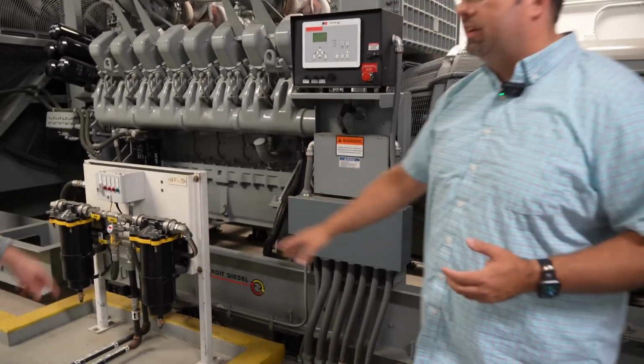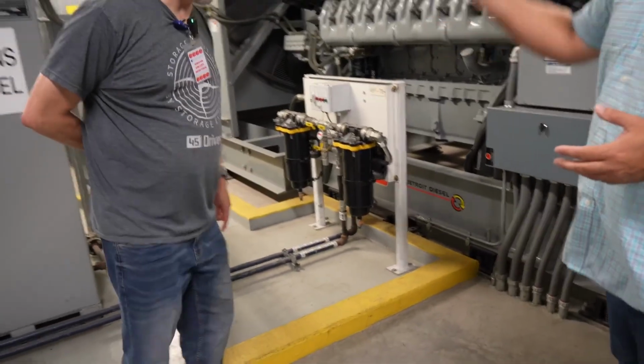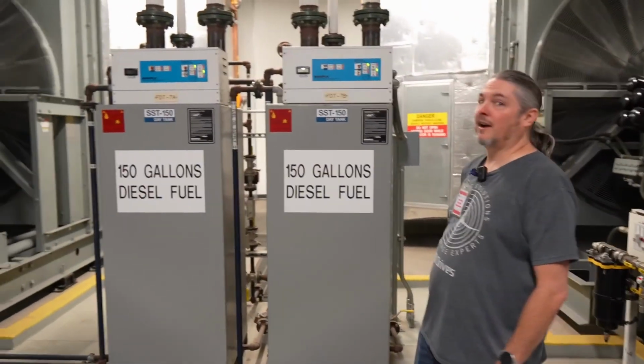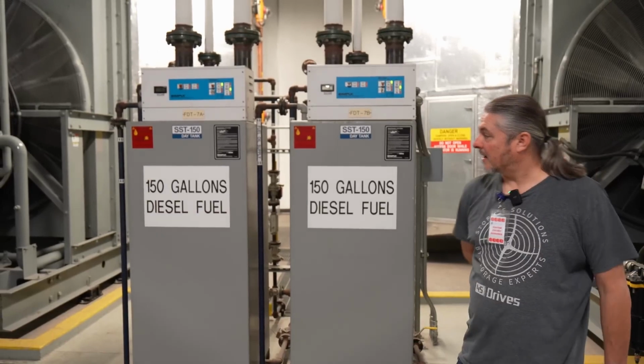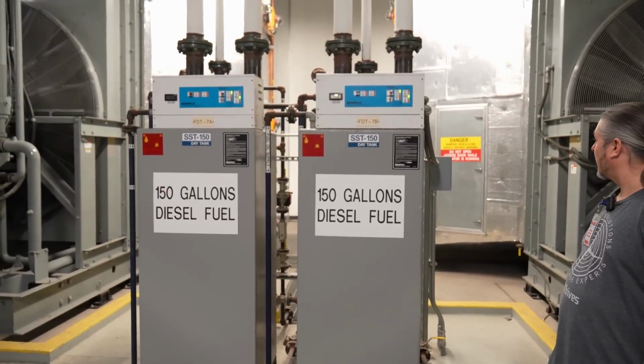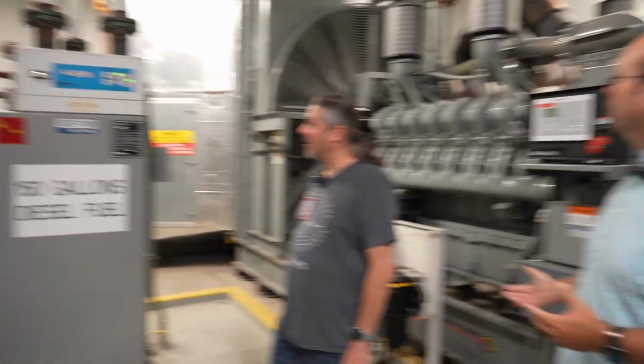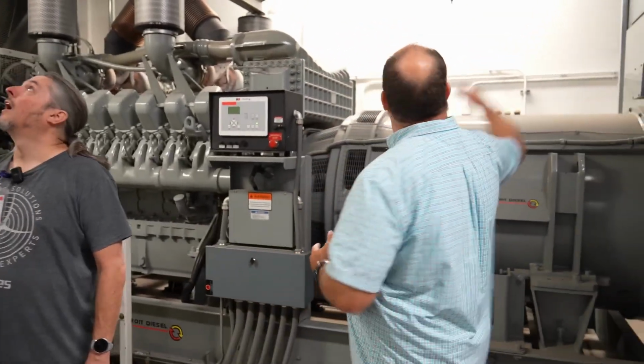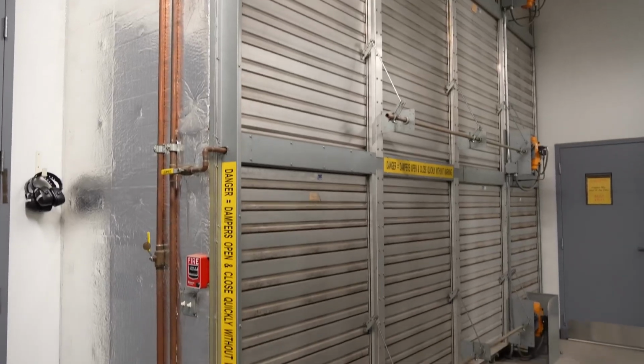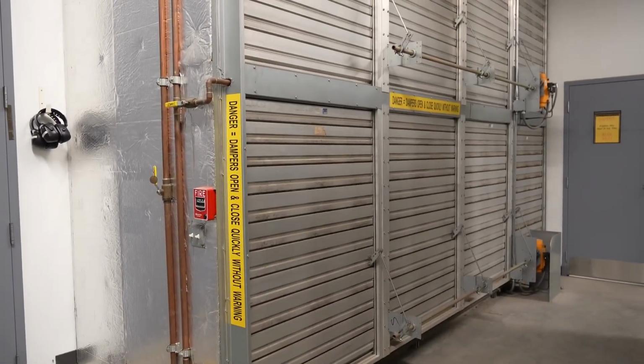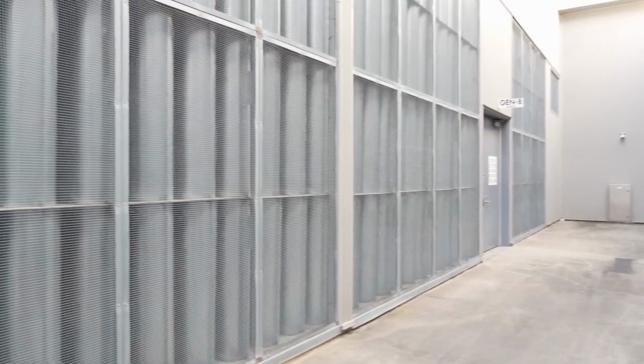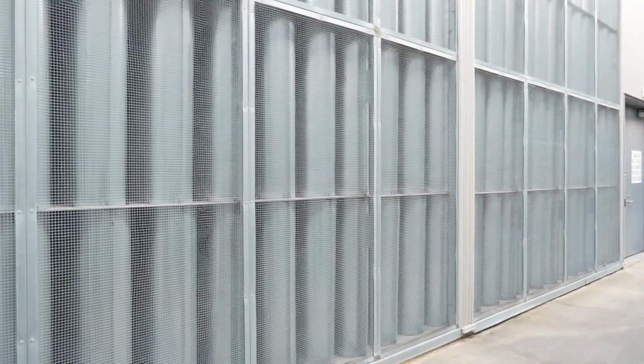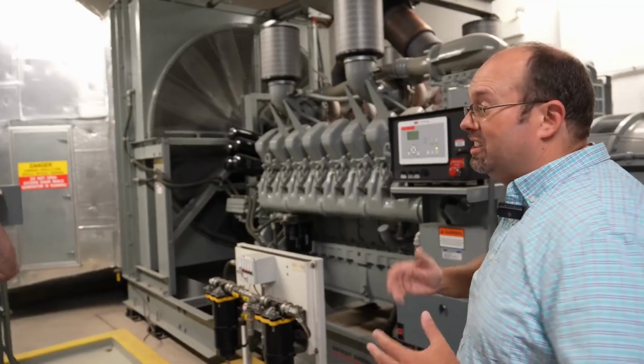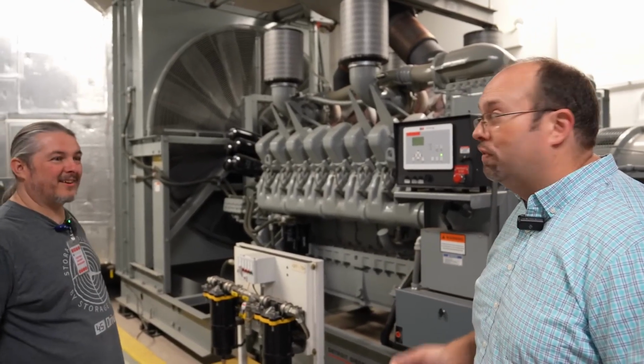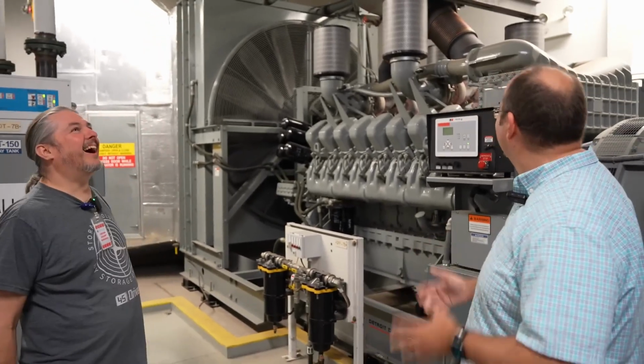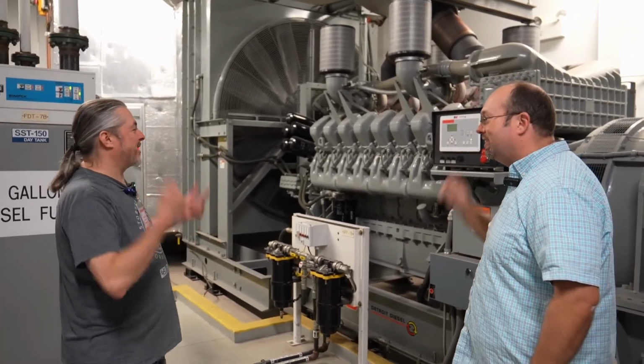You'll notice a raised barrier to deal with fuel containment in case there is an issue. Yep. And then usually you would have what we call a day tank, which is a small fuel storage on-site next to the generators, able to provide fuel immediately if they were to kick on. In this situation, the cold air comes in from this side of the building, gets sucked through the radiator, and then out the louvers on the back side. That will all automatically open up when these things are requested to turn on. And again, these things go from sitting still, not on, to a full 60 mile an hour, ear-bleeding rush in about 16 seconds.